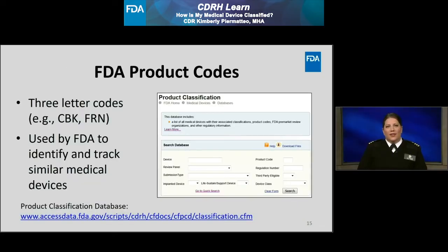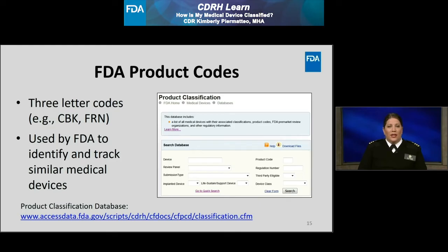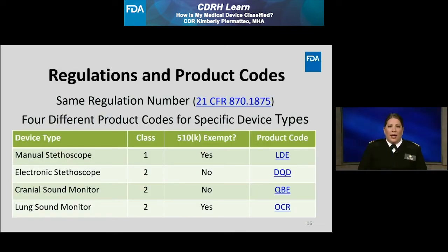When discussing the device class and extent of regulatory requirements, it's important to mention FDA product codes. FDA product codes are three-letter codes used to identify and track similar devices. If you are able to determine the appropriate FDA product code for your device, you can then easily determine the applicable regulatory requirements. Product codes can be found by searching the FDA's Public Product Classification Database. Within the CFR, the FDA has classified various device types based on risk. Each regulation number may have one or more associated product codes which are classified differently and have different regulatory requirements.